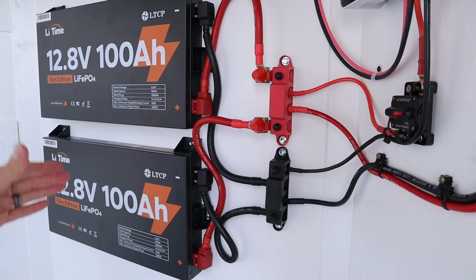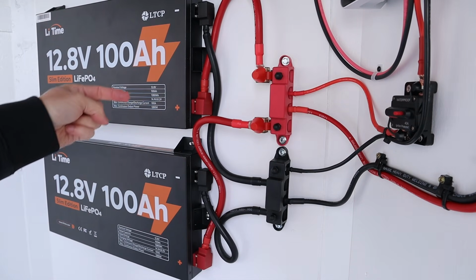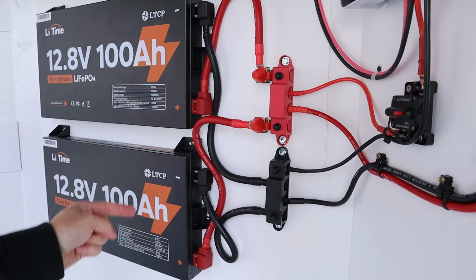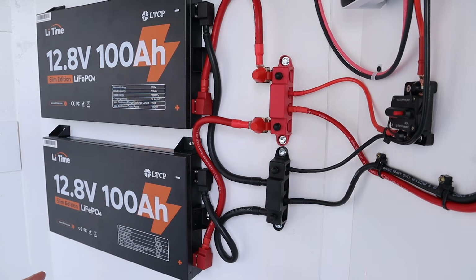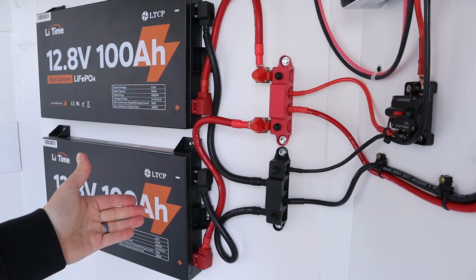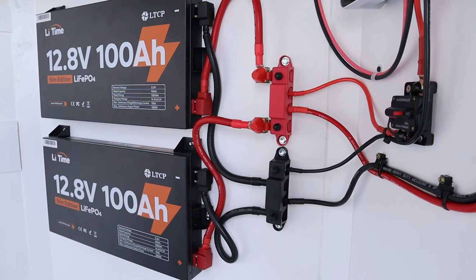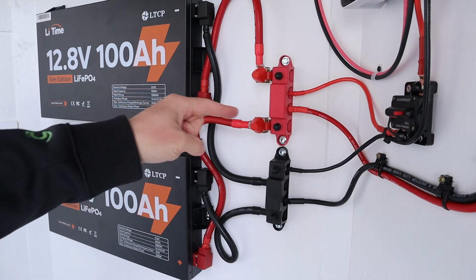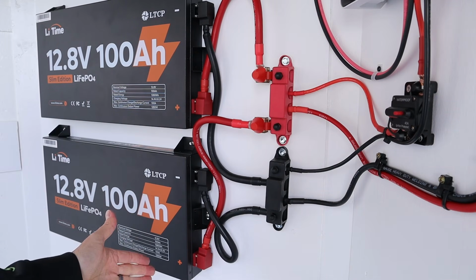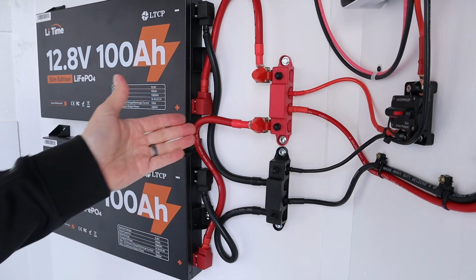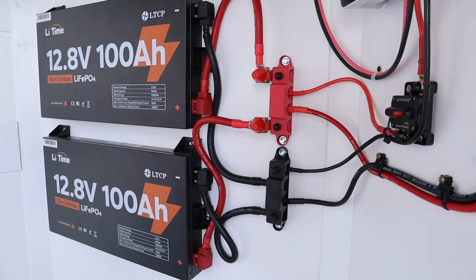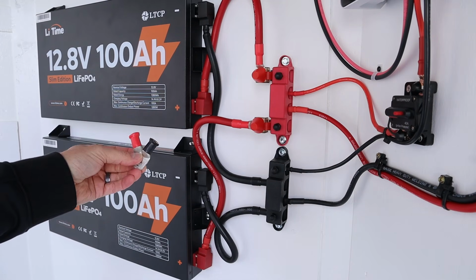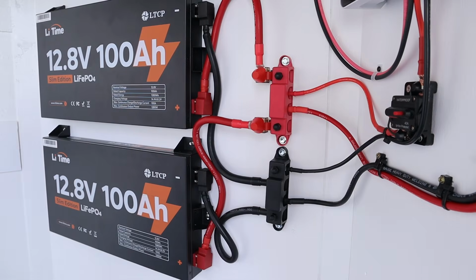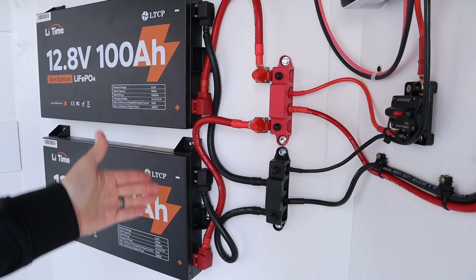Now, after going through the full install of these batteries and bus bars, my only complaint is that the size of the ring terminals on the batteries are 1/4 inch. And so when you're using heavy duty wire like this with these 150 amp fuses, everything is in 5/16. So I could not find 1/0 wire that would go to 1/4 inch terminals on one end and 5/16 on the other. So I had to purchase cables. I had to cut off the 5/16 ends and then recrimp on 1/4 inch to make these connections.